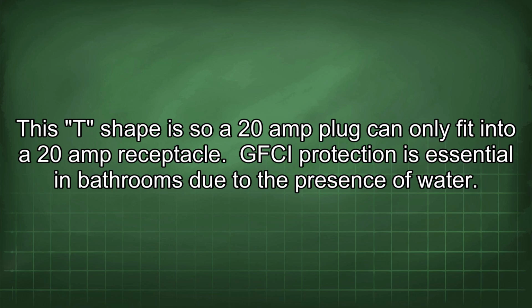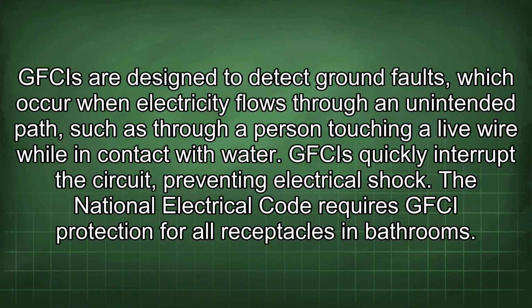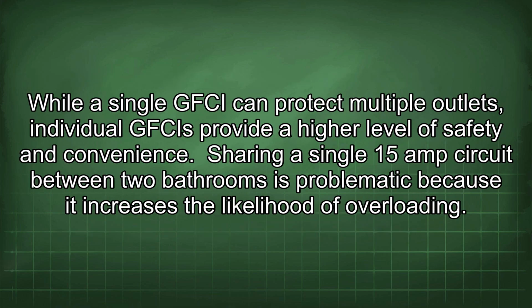GFCI protection is essential in bathrooms due to the presence of water. GFCIs are designed to detect ground faults, which occur when electricity flows through an unintended path, such as through a person touching a live wire while in contact with water. GFCIs quickly interrupt the circuit, preventing electrical shock. The National Electrical Code requires GFCI protection for all receptacles in bathrooms. While a single GFCI can protect multiple outlets, individual GFCIs provide a higher level of safety and convenience.